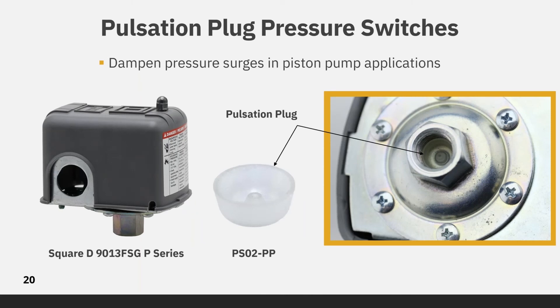The pulsation plug slows the flow of fluid to the diaphragm of the pressure switch to reduce the surge rate. The most common application for the switch with the pulsation plug is for piston pumps. Without the plug, the spike in pressure would cause the contacts to open, shutting off the power to the pump only to be turned right back on. The pulsation plug can be easily installed into any brand of switch with a quarter inch FPT pressure connection.